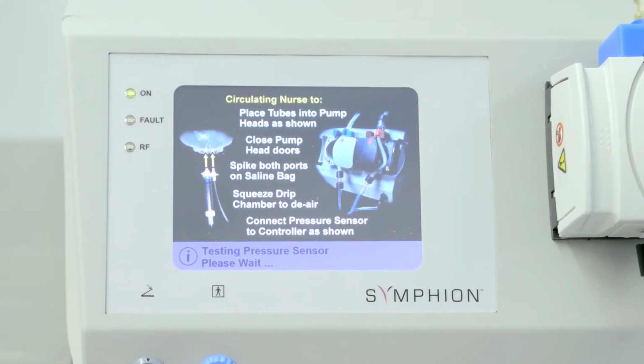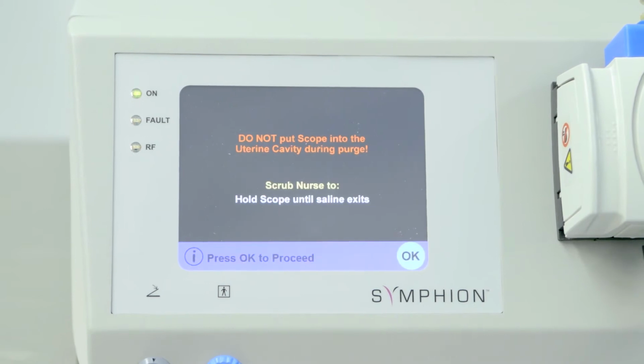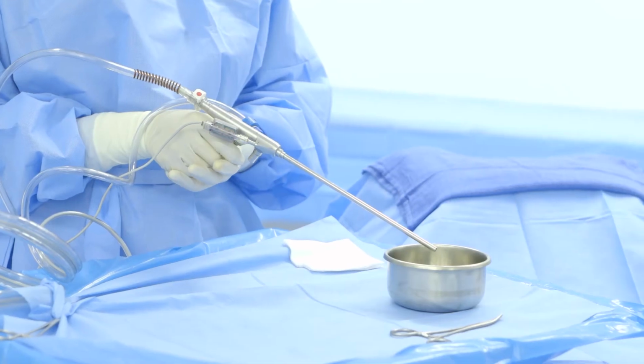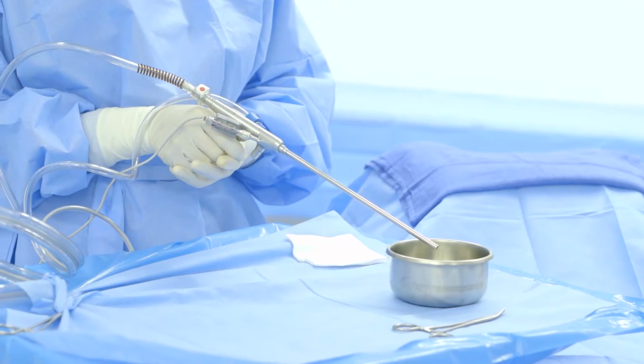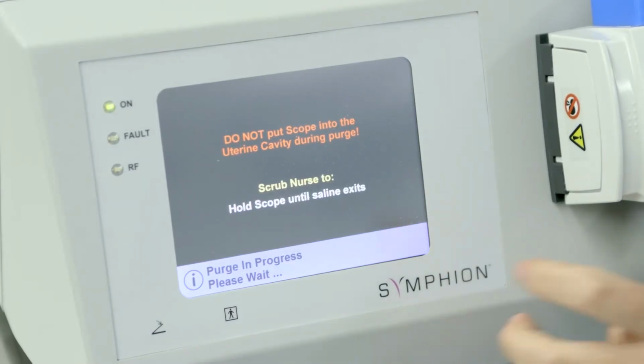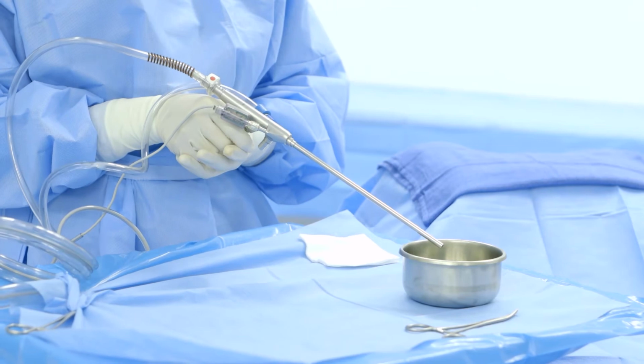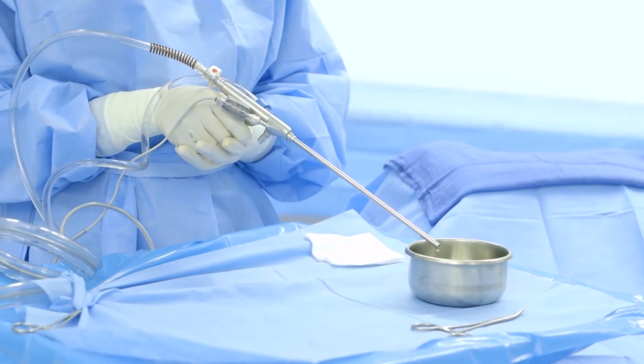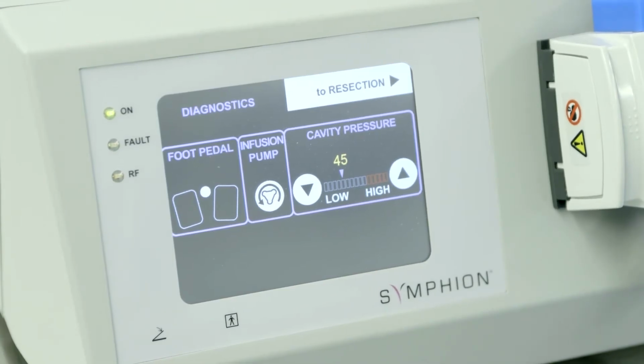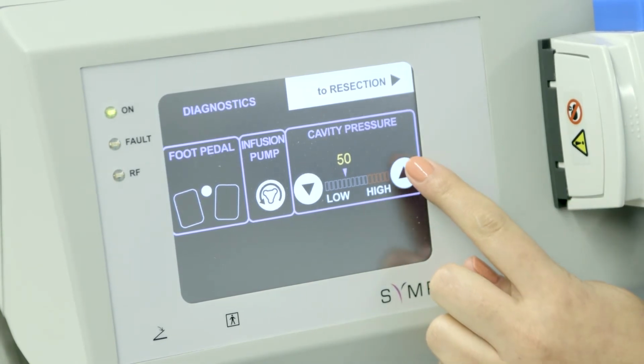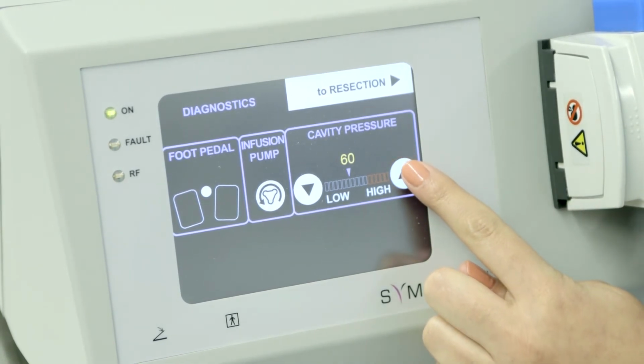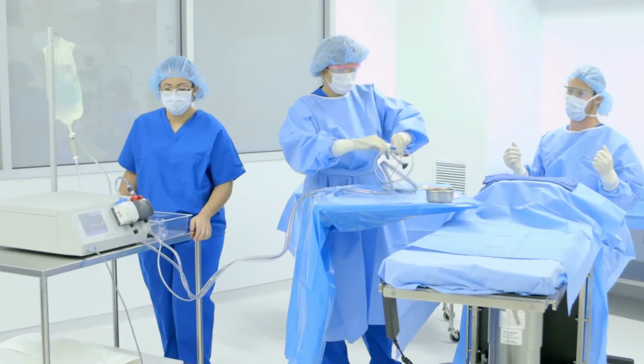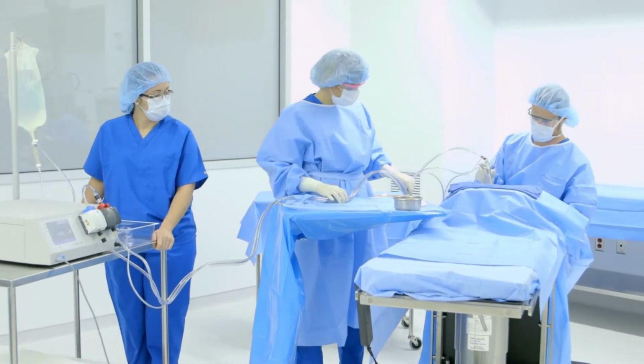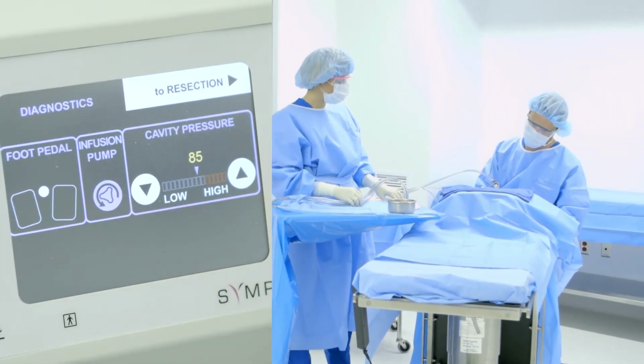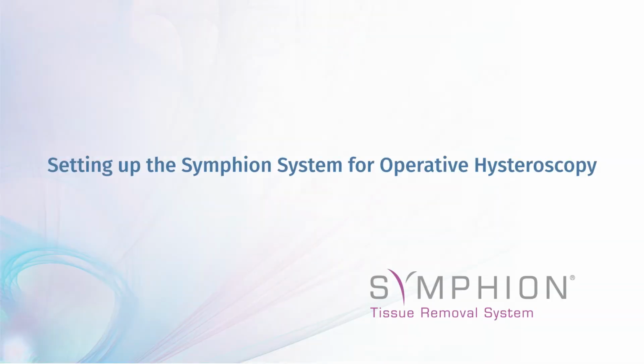The controller will run the pressure sensor self-test for approximately 5 seconds. Hold the scope in the sterile field over an empty receptacle and press OK to purge the system. Wait 9 seconds until the purge completes. The controller will enter diagnostic mode. In diagnostic mode, you will need to set the desired cavity pressure by pressing the up arrow on the controller screen. The endoscope is now ready for insertion into the uterine cavity. Infusion of saline will start when the button labeled Infusion Pump is pressed. Follow standard diagnostic hysteroscopy practices.